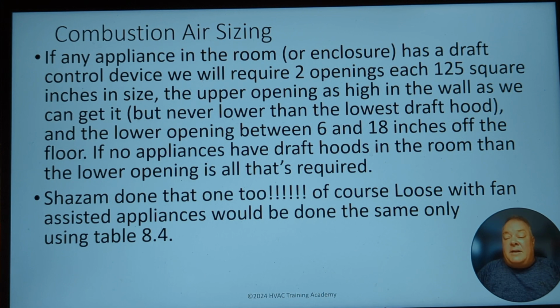Now, if they're both fan assisted in that room, we only need 1 opening, right? We'd only need a 125 square inch opening between 6 and 18 inches. So they call the lower opening the combustion air opening. They call the upper opening, when you have draft hoods, a ventilation air opening.